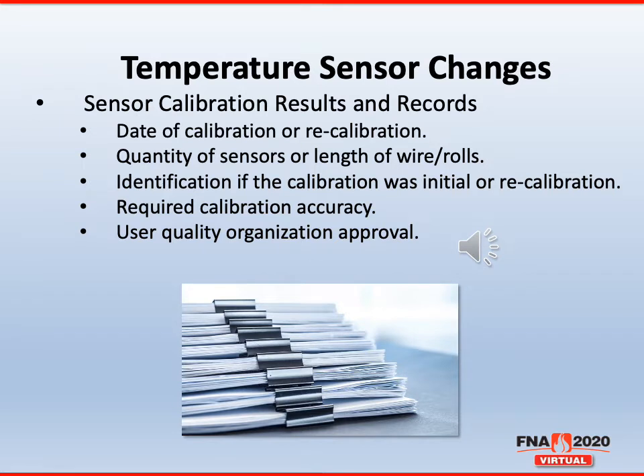There are a few new changes when it comes to the documentation for temperature sensors for results and records. Obviously, we'll need the date of calibration or recalibration. We need to know the quantity of sensors, or if you're purchasing a spool in rolls or lengths of wire, we need to know the length of the wire. Identification if this is an initial calibration or a recalibration of the sensors. We need to know the required calibration accuracy, which again is going to be the special limits of error, plus or minus 2 or 0.4% of reading. And then the user's quality organization shall approve these certifications.